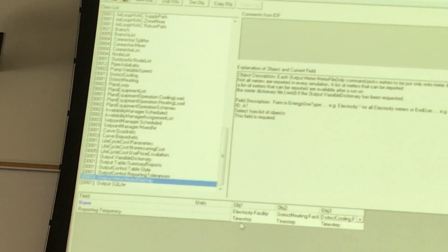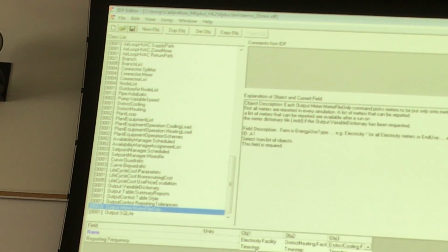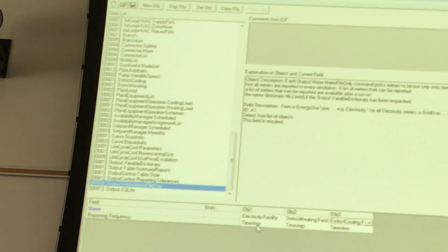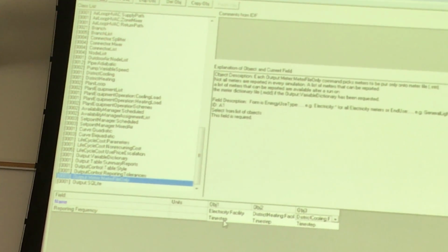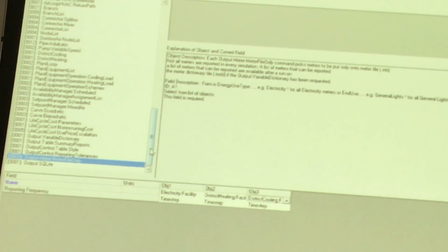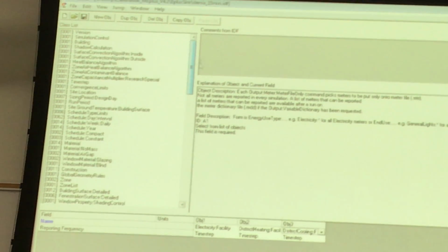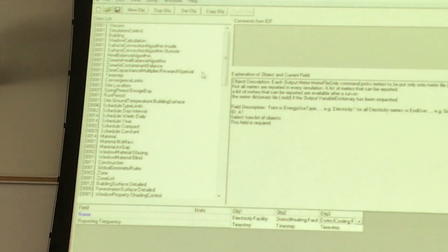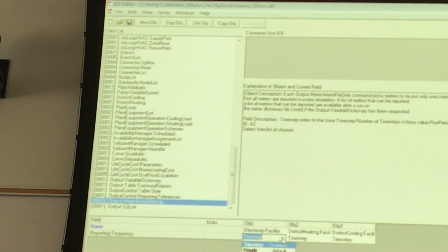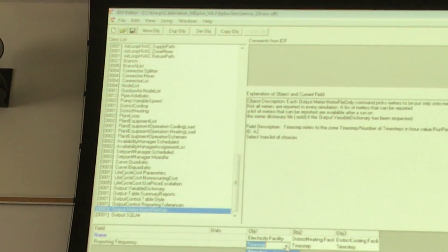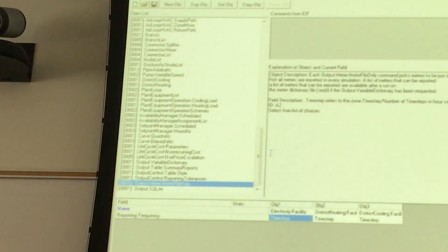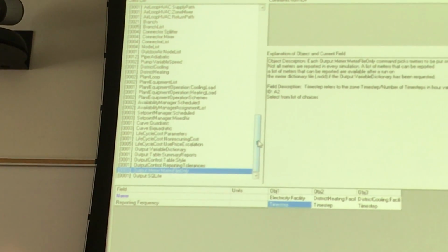And for each of them the reporting frequency will be time step, which means whatever time step you have, you'll get that time of output. So there's some issue I want to discuss here. If you are calibrating to monthly, it will be totally fine. You can just change this to hourly, monthly, or daily accordingly. That's very straightforward.